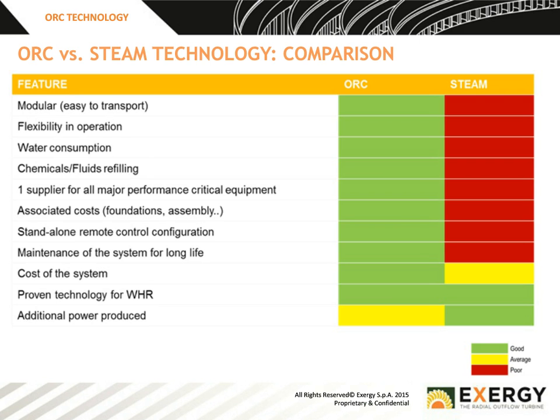Flexibility of operation. ORC is extremely good at working down to very low loads, and I'm talking approximately 10% of the input power of the nominal. So ORC is extremely flexible, and if you have a process or an application where the engines may vary in load, then ORC can be a very good solution.